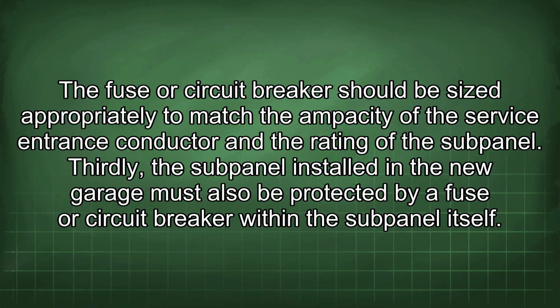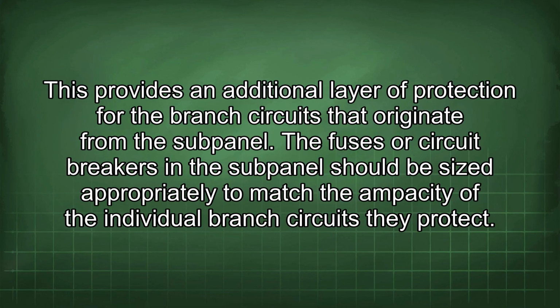Thirdly, the subpanel installed in the new garage must also be protected by a fuse or circuit breaker within the subpanel itself. This provides an additional layer of protection for the branch circuits that originate from the subpanel. The fuses or circuit breakers in the subpanel should be sized appropriately to match the ampacity of the individual branch circuits they protect.